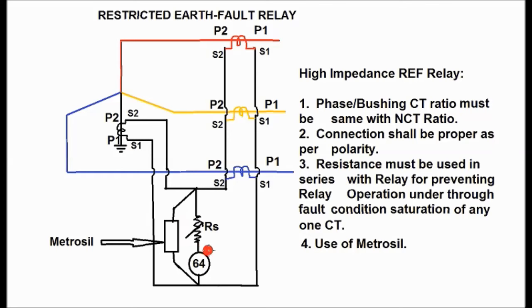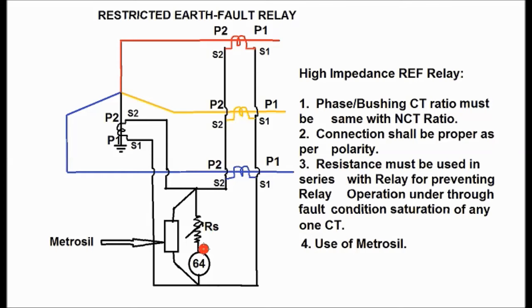It is connected to the restricted earth fault relay, designated as 64. A high impedance is connected in series with the relay — that is why it is called the high impedance relay. The function of the high impedance is to prevent tripping and provide stability during through-fault conditions if any of the neutral CT, phase CT, or bushing CT saturates. Since high impedance is connected in series with the relay, a voltage spike may occur during internal fault conditions, so a varistor is connected across the relay and resistance combination to avoid damage.